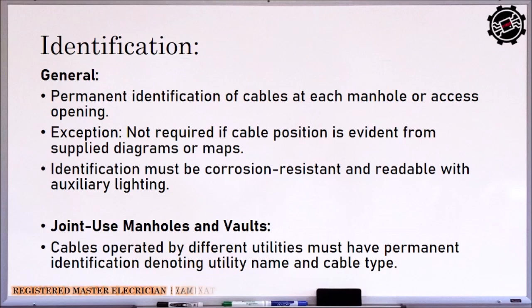Okay? So joint use manholes and vaults. So cables operated by different utility must have permanent identification denoting the utility name and the cable type. So if the manholes are used by different company, magkaiba, dapat ang kanilang mga wires or cables, dapat the identification must denote the name of the company at kung para saan yung cable, either that is supply or communication cable.